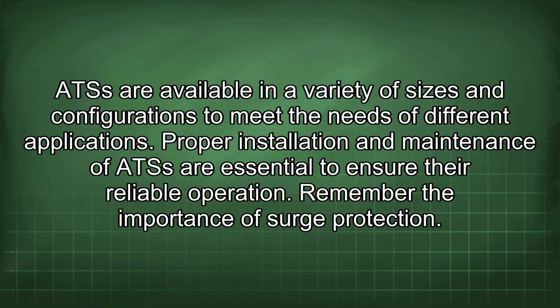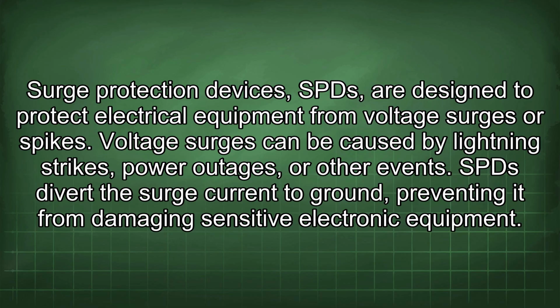Remember the importance of surge protection. Surge protection devices, SPDs, are designed to protect electrical equipment from voltage surges or spikes. Voltage surges can be caused by lightning strikes, power outages, or other events. SPD divert the surge current to ground, preventing it from damaging sensitive electronic equipment.